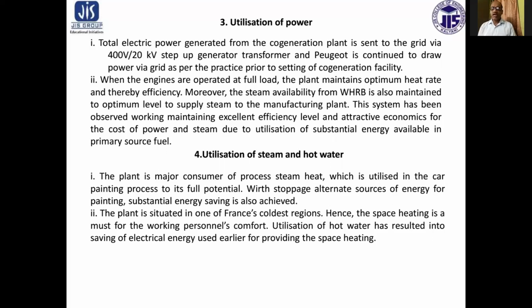When the engines are operated at full load, the plant maintains optimum heat rate and thereby efficiency. Moreover, the steam availability from the waste heat recovery boiler is also maintained at an optimum level to supply steam to the manufacturing plant. The system has been observed working at excellent efficiency levels and attractive economics for the cost of power and steam, due to utilization of substantial energy available in the primary source fuel.